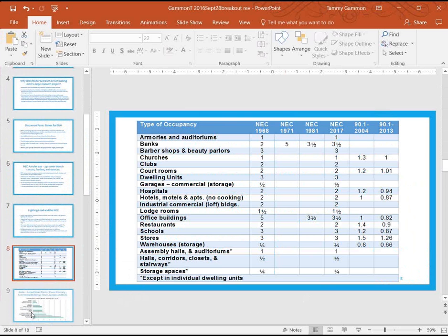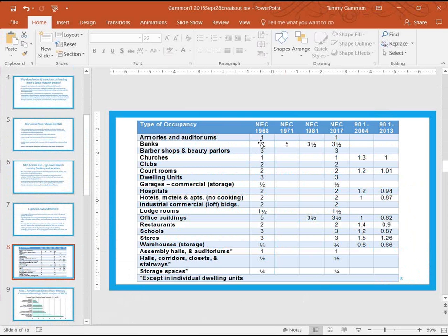In 1968 we see these numbers, and I'm showing the changes that have occurred, finishing with the 2017 values. Since 1968, the requirement for banks went up to 5 watts per square foot, then was reduced to 3.5 in 1981. Office buildings went from 5 watts per square foot in 1968, also reduced in 1981. Those are the changes over the last 50 years. Since the NEC applies to about 150 million electric utility customers, that warrants a second look at what's going on. I think it's time for the NEC to at least consider that changes need to be made here.